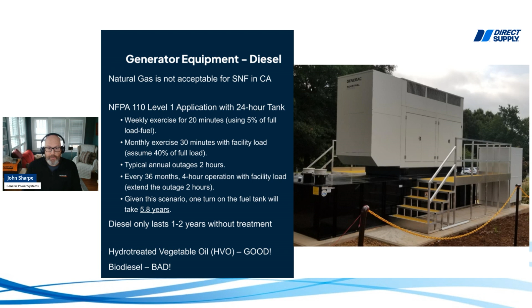The problem is it's really, really unstable. It only lasts maybe 6 months. So in a stored system like this, not an option. No manufacturer is going to bless this for the long term. Everyone in this industry is not a fan. Biodiesel is great for buses because they burn it constantly, running all the time - it doesn't sit there for 9, 12, 15 months at a time. That's why biodiesel is bad, HVO is good.